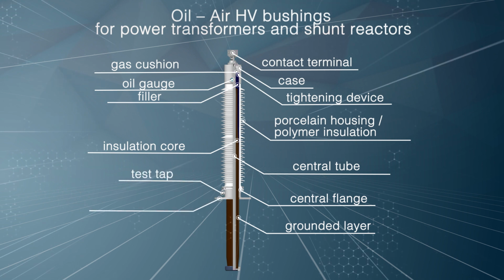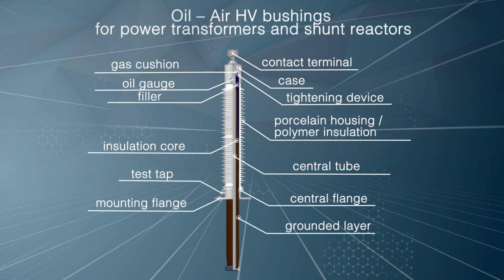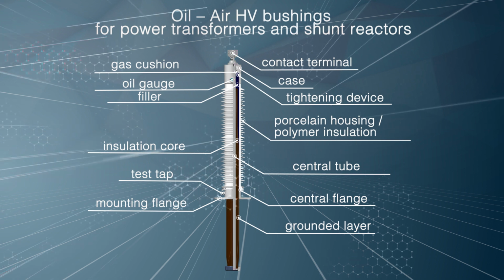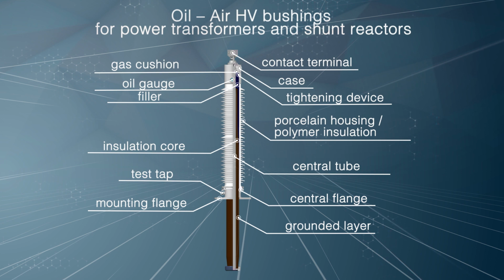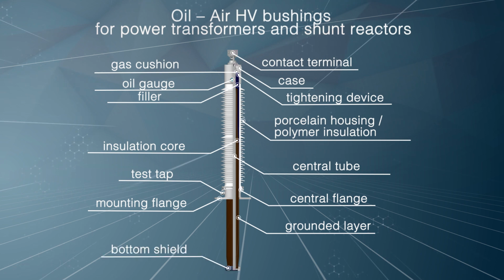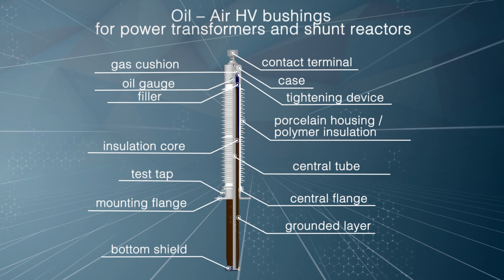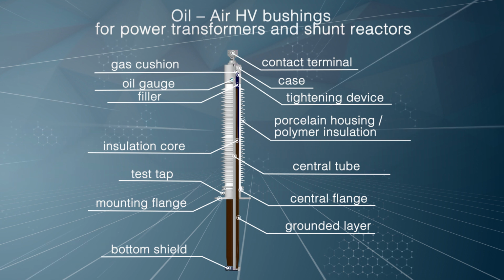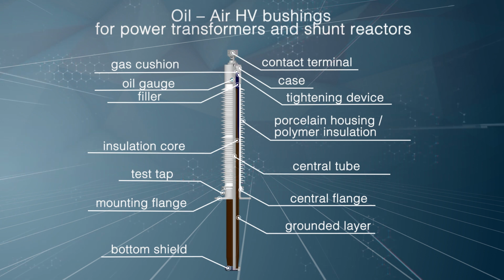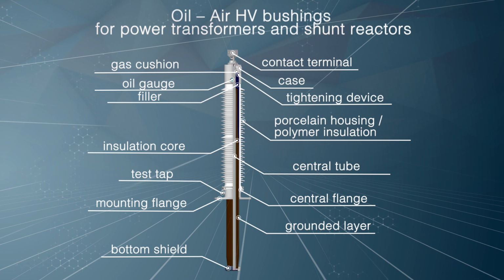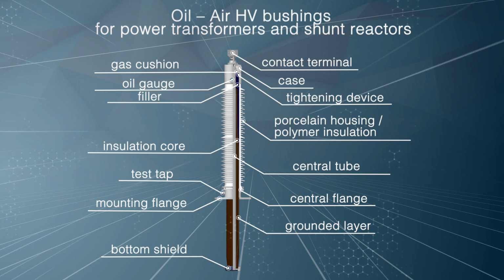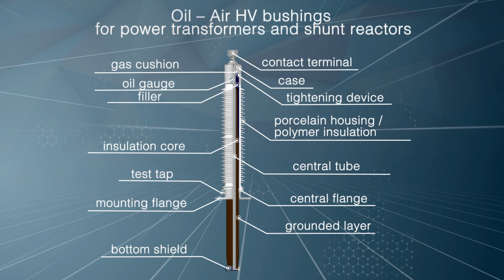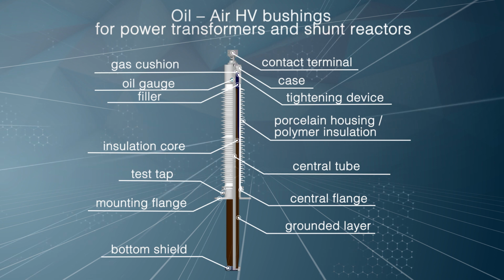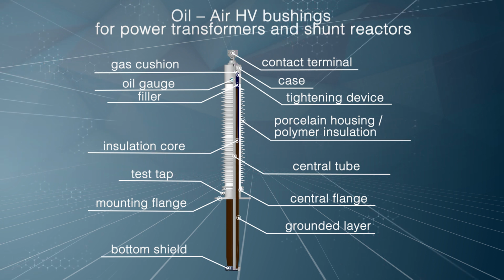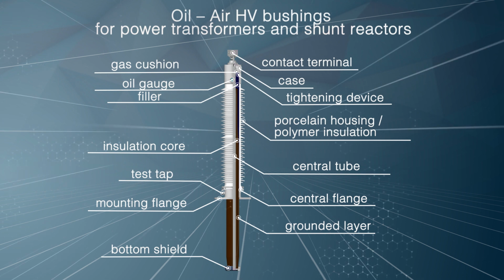Sometimes the mounting flange is combined with the central flange. The bottom shield equalizes external electric field in the bottom part of the bushing. The top shield is used in designs of bushings with polymer external insulation for equalizing electric field in the top part of the bushing. In bushings with porcelain housing, the top shield function is performed by the case.